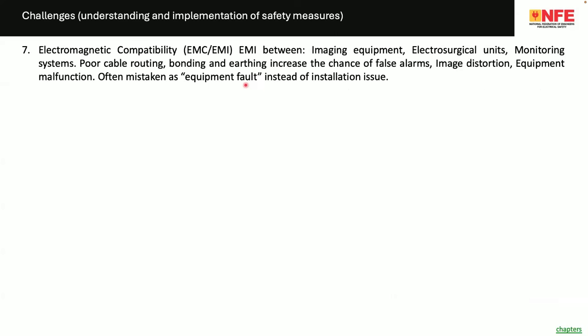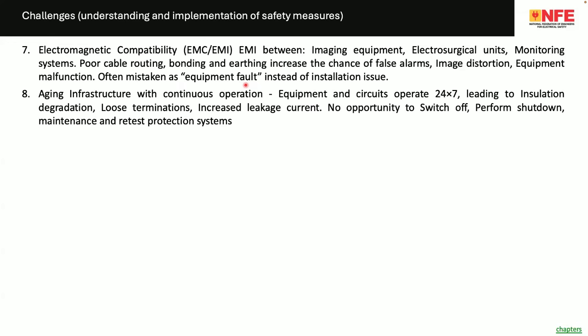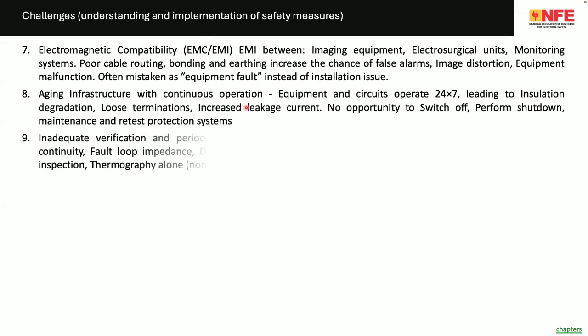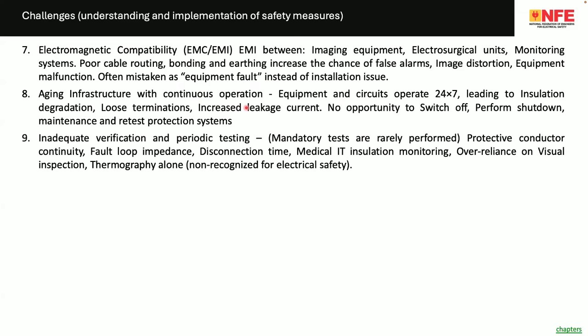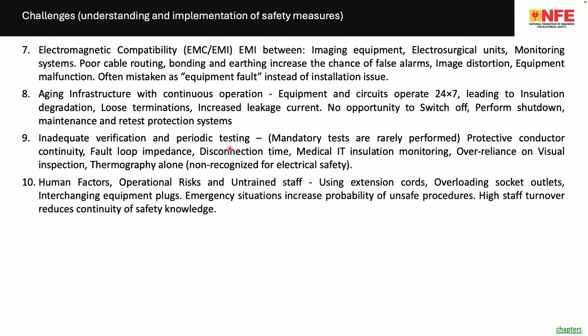These are installation problem. When you switch on an electrocautery machine, and if it is creating a disturbance in the nearby equipment, it's not the problem of the electrocautery machine. It is not a fault of the equipment. This is an installation problem, because you have not taken care of the EMI very much. Aging infrastructure with continuous operation, inadequate verification and periodic testing. In most of the cases, this is a very challenging situation. I have the recommendation. So in the recommendations, I will explain a little bit more.